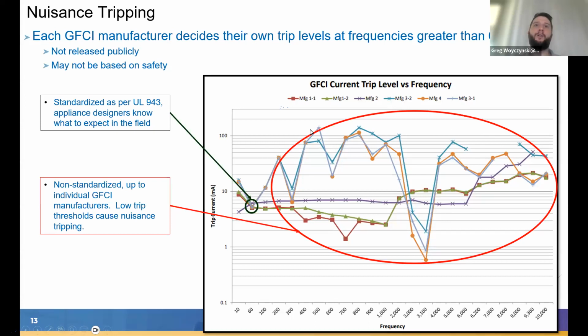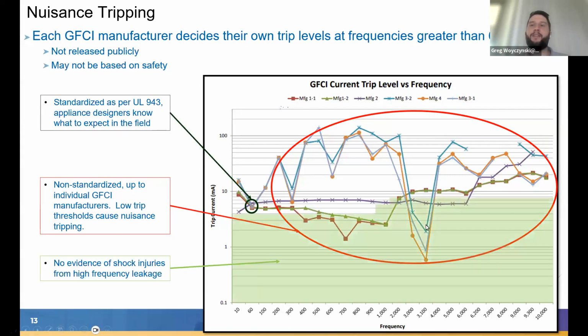The problem with this graph is all of this in the red circle. The non-standardized high frequency trip thresholds that GFCI manufacturers are putting out there today. The big issue here is that these trip levels are happening on safe levels of electricity. So this green block is actually drawn conservatively. If I was really scientific about it, it would be a curve going up like this. But all of these points in the green block, these are safe electrical signals proven by third-party studies, and there is no reason for the GFCI to be tripping down here. But the GFCIs are tripping down here, down at 5.5 milliamps. No danger here to a consumer, but we have GFCIs tripping down here because they can, because the UL 943 standard says that's okay. The UL 943 standard is agnostic to those high frequencies.